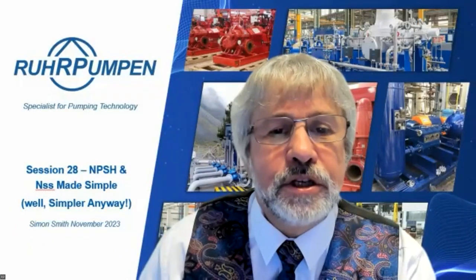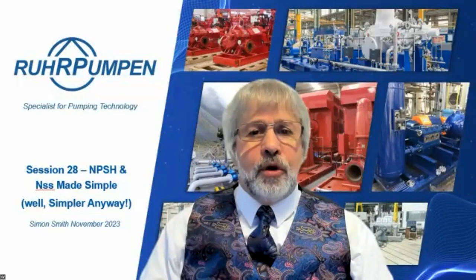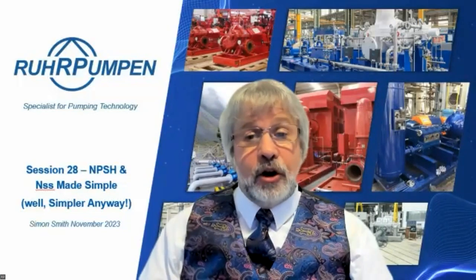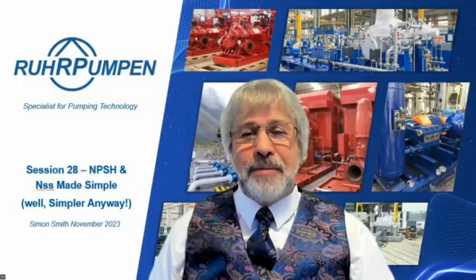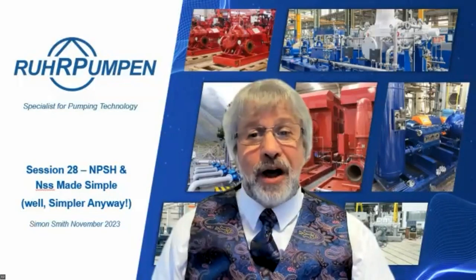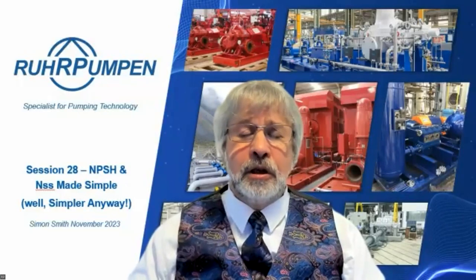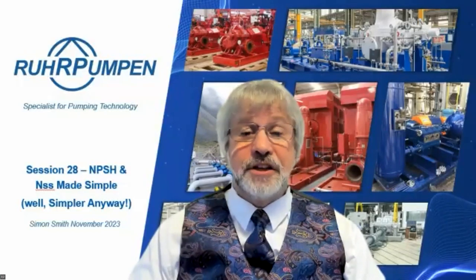Mustafa Abuzaid asks: when choosing a new pump, should we calculate the RPM from the NSS equation to avoid cavitation? What you need to do is calculate your NPSH available and then look at the marketplace to see what is available. If you've got three meters of NPSH available, look for pumps that can deliver two meters NPSHr - possibly a VS6 zero-NPSH pump. Speak to several vendors and then consider whether you need to increase your NPSH available.